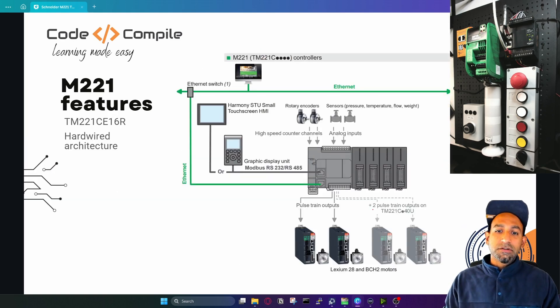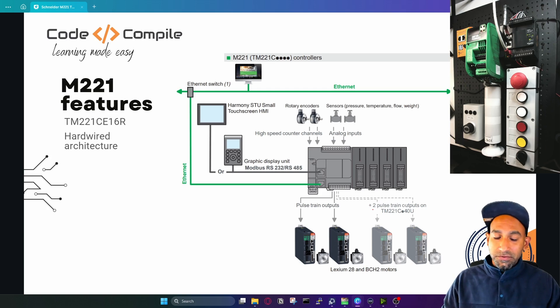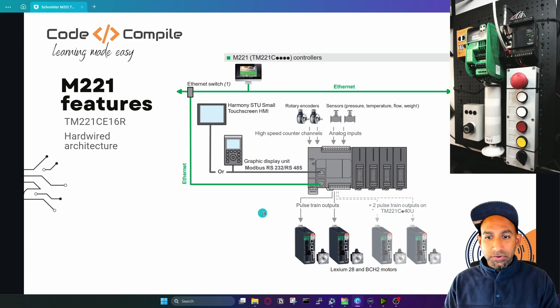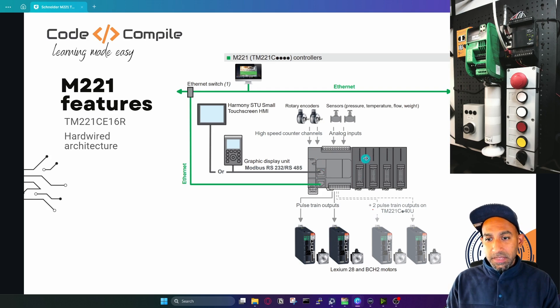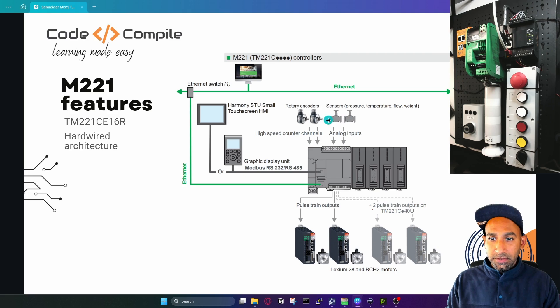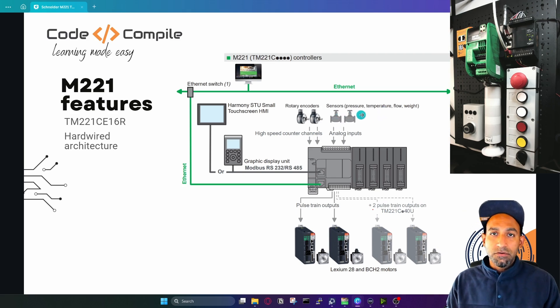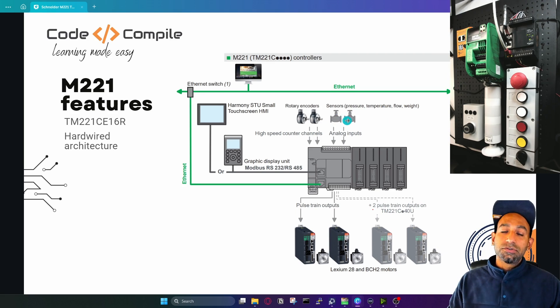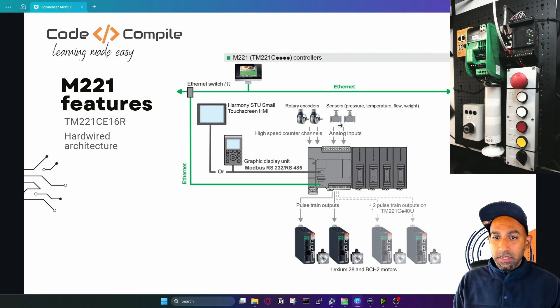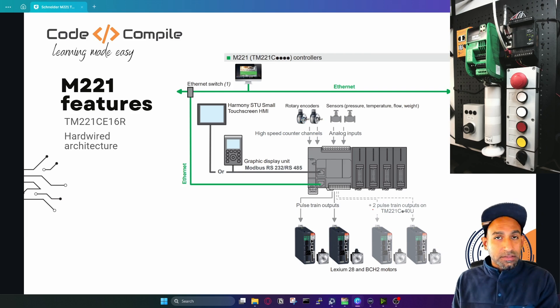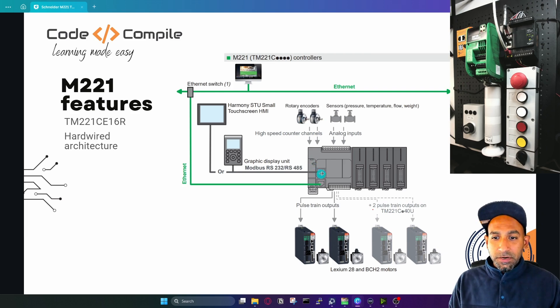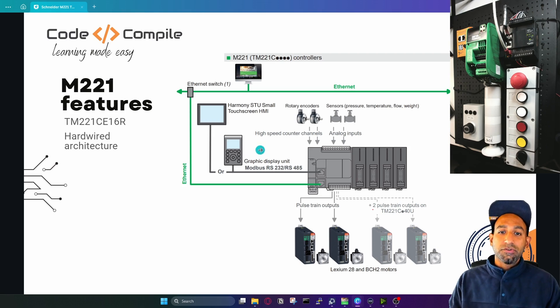First, you need to download the software, then we'll continue with the architecture. This is the PLC with some extra modules. You can connect two analog inputs, so here you can see sensors — pressure, temperature, flow, or weight — which give zero to ten volt signals to the PLC. You can connect a rotary encoder for high speed counter channels. From the RS-485 or RS-232 serial communication, you can connect a graphical display unit or HMI.